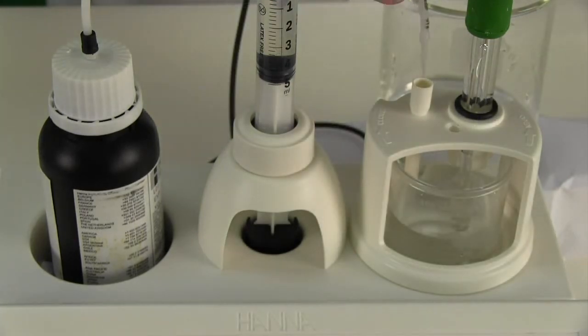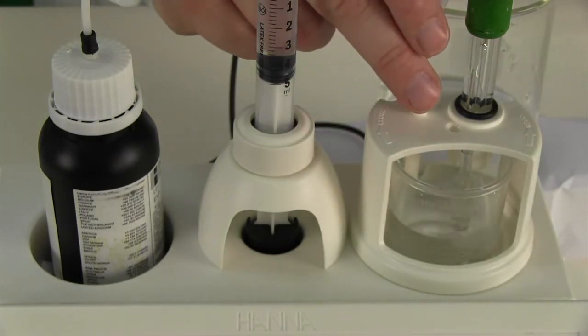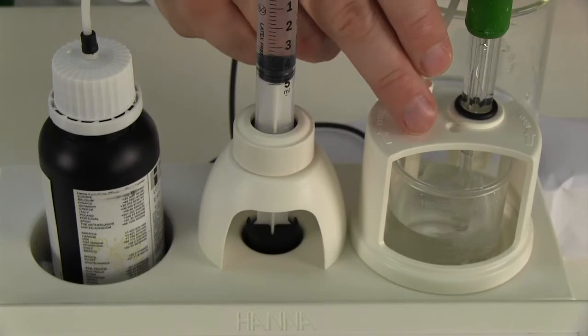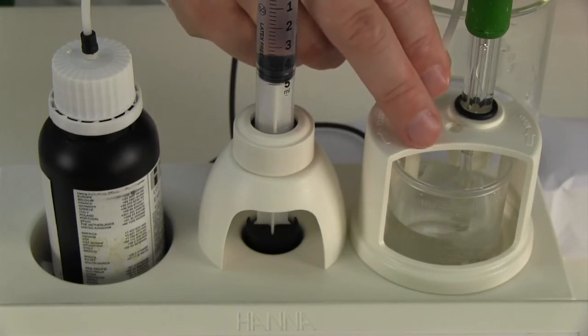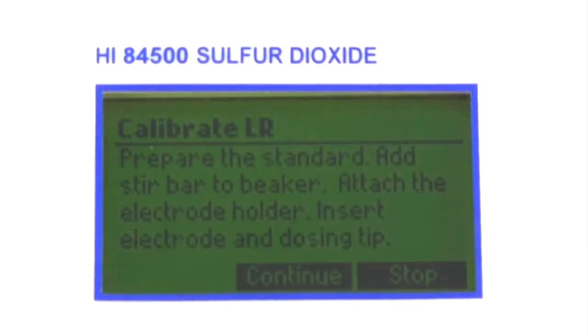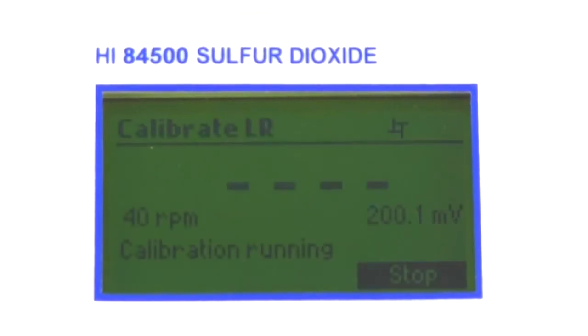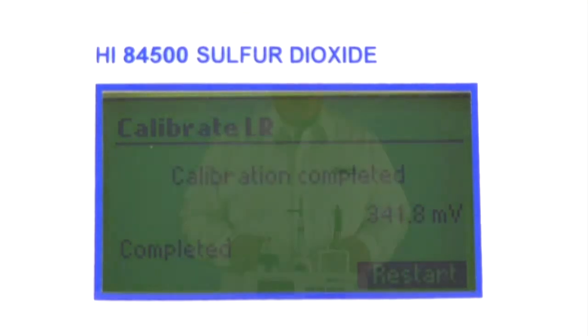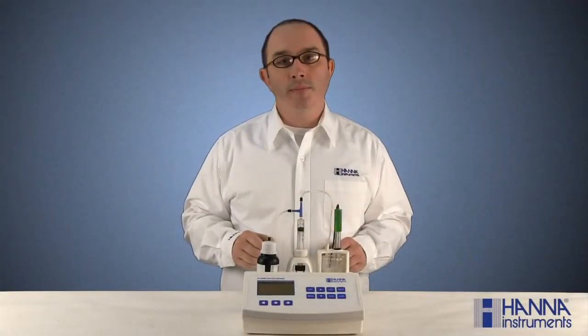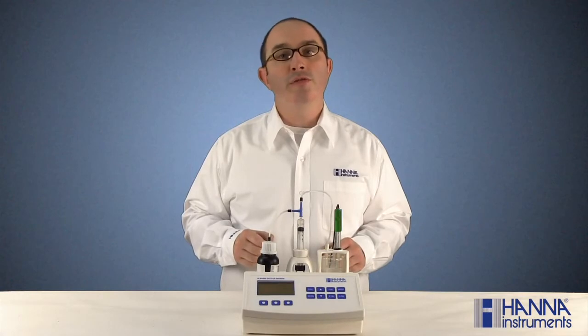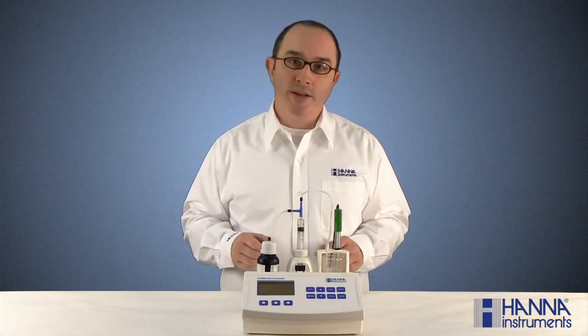Insert the dosing tip into the tube sleeve. It is critical that the tip be submerged about a half a centimeter into the solution. Finally, select Continue to begin the calibration. When finished, calibration completed will display. And that's how you install and calibrate the pump on our HI-84500 free and total sulfur dioxide mini titrator.